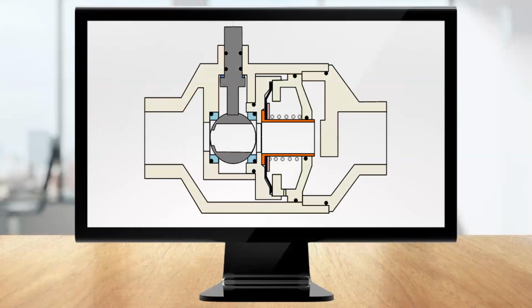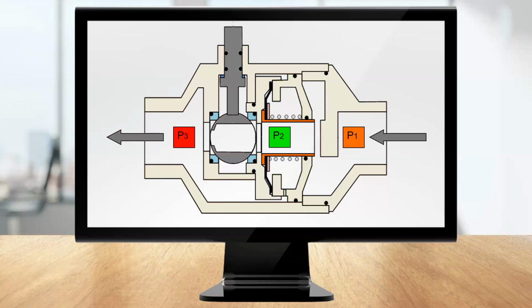So let's take a look at pressure-independent valves. There are two ways to make valves pressure independent. The first is a mechanically regulated pressure-independent valve. The valve is designed so that a variable amount of pressure is consumed by the regulator and the control portion, or ball, always sees that same pressure going across it. The flow goes right to left. P1 is your inlet pressure to the valve. P2 is the pressure after the loss going through the regulator. And P3 is the pressure after the loss going through the valve.